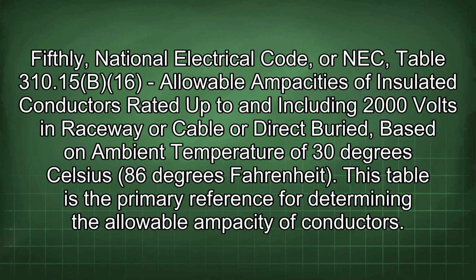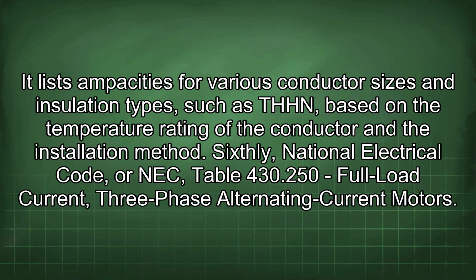Fifthly, NEC Table 310.15(B)(16) allowable ampacities of insulated conductors rated up to and including 2000 volts in raceway or cable or direct buried, based on ambient temperature of 30 degrees Celsius, 86 degrees Fahrenheit. This table is the primary reference for determining the allowable ampacity of conductors. It lists ampacities for various conductor sizes and insulation types, such as THHN, based on the temperature rating of the conductor and the installation method.